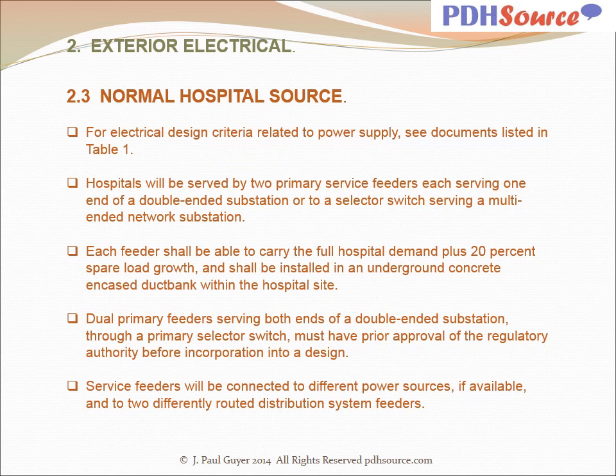For electrical design criteria related to power supply, see documents listed in Table 1. Hospitals will be served by two primary service feeders, each serving one end of a double-ended substation, or to a selector switch serving a multiple-ended network substation. Each feeder shall be able to carry the full hospital demand plus 20% spare load growth, and shall be installed in an underground concrete encased duct bank within the hospital site.